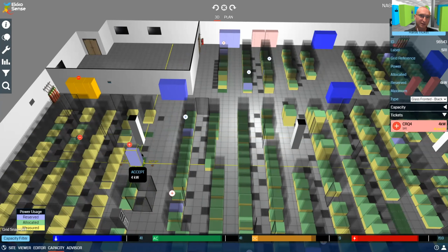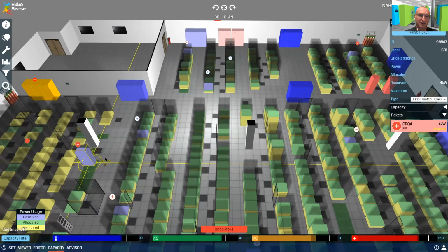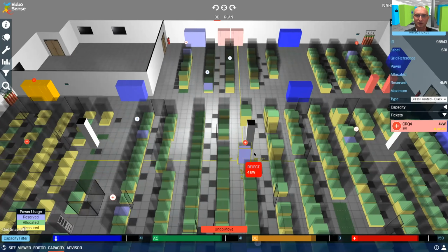You can drag this rack around to find an appropriate location. We've got locations here that the software would happily accept the change. But if I drag it over to a different part of the room, it might reject it, either through positions of equipment, not enough space in the aisles, or no cooling. Here, even though there's clearly space for a new rack, it's going to reject the change because there's not enough cooling to be sure that change can be safely made.